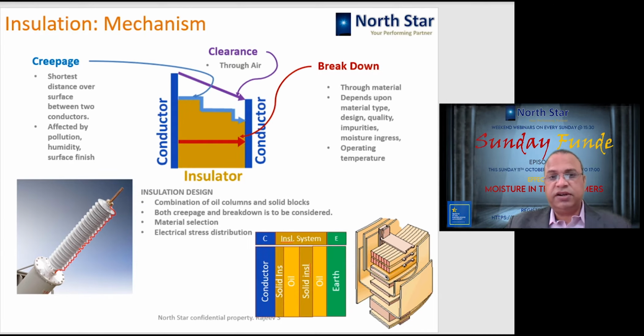So you can see here the red arrow, the insulation is breaking down, and this breakdown strength depends upon various factors: the material type, the design of the insulation, quality, impurities in the insulation, what moisture it is subjected to, and what operating temperature the system is working at.